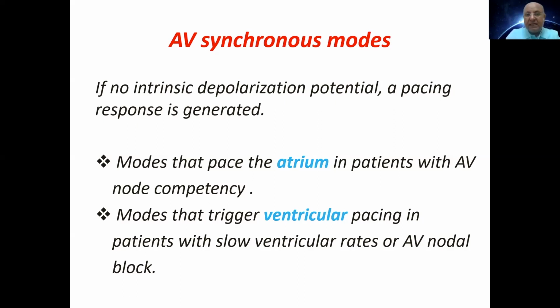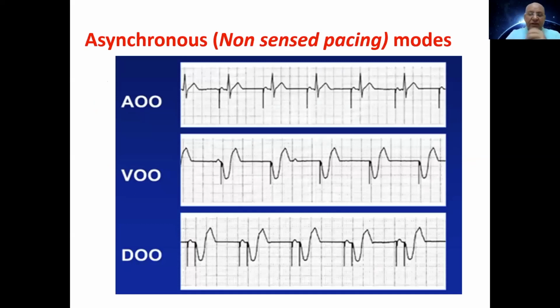This is the synchronous mode. Asynchronous mode is very important; you have to know what it is. Asynchronous mode means non-sensed pacing. Regardless of any intrinsic activity or depolarization of the chamber, the pacemaker will give a preset number of pacing impulses to the patient. So if you look at AOO, A is pacing the atrium, O means no sensing of the atrium: non-sensing, but pacing the atrium. So when you find AOO or VOO, it means non-sensed pacing. Keep it in mind because it is very important later on.